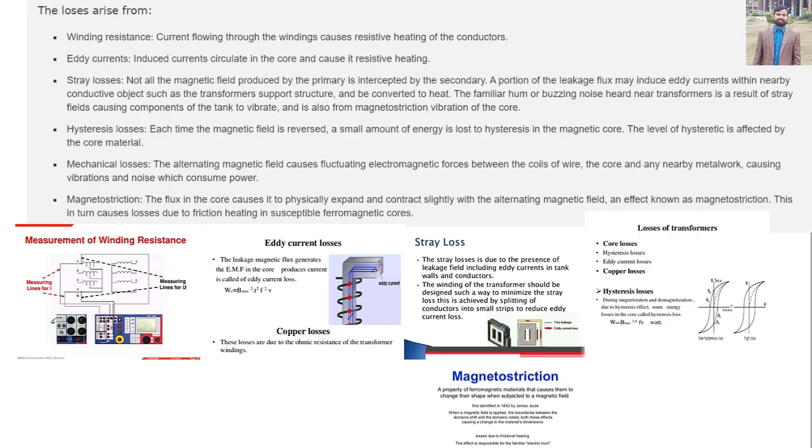A portion of the leakage flux may induce eddy currents within a nearby conductive object such as the transformer support structure and be converted to heat. The familiar hum or buzzing noise heard near transformers is a result of stray fields causing components of the tank to vibrate and is also from magnetostriction vibration of the core.